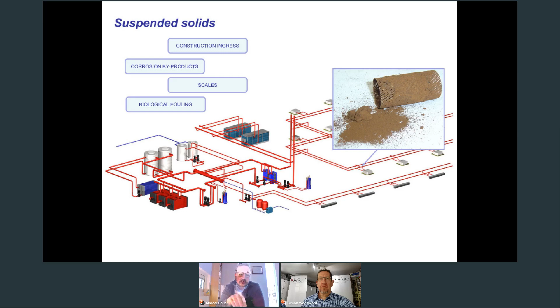Now, our technology is the ENWA, and this is an all-in-one side stream filter and water treatment unit, which eliminates the need to dose conventional corrosion inhibitor chemicals. It provides pH elevation to a range of 9 to 10.5, which is suitable for steel and cast iron components. The full treatment unit is not suitable for systems that contain aluminium, but it can be used as a filter-only unit in those instances.